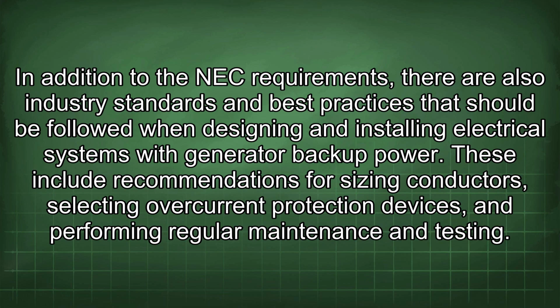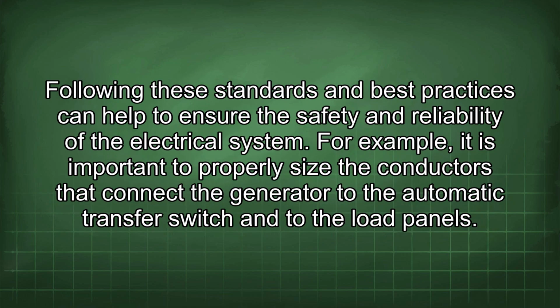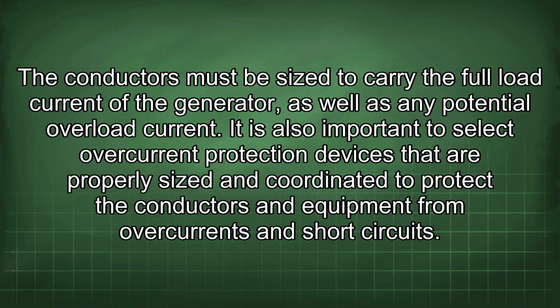These include recommendations for sizing conductors, selecting overcurrent protection devices, and performing regular maintenance and testing. Following these standards and best practices can help to ensure the safety and reliability of the electrical system. For example, it is important to properly size the conductors that connect the generator to the automatic transfer switch and to the load panels. The conductors must be sized to carry the full load current of the generator as well as any potential overload current. It is also important to select overcurrent protection devices that are properly sized and coordinated to protect the conductors and equipment from overcurrents and short circuits.